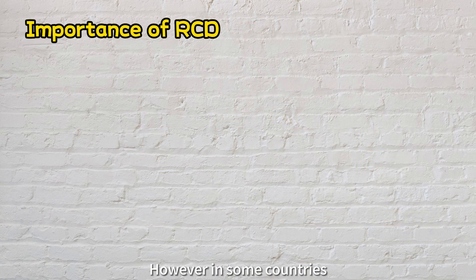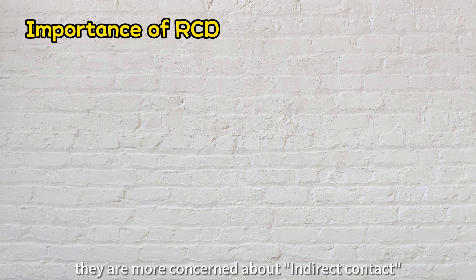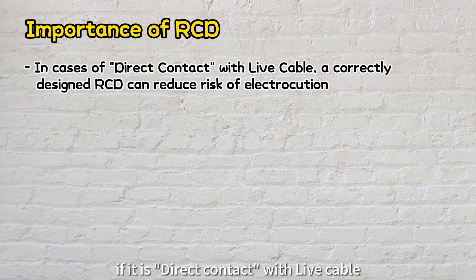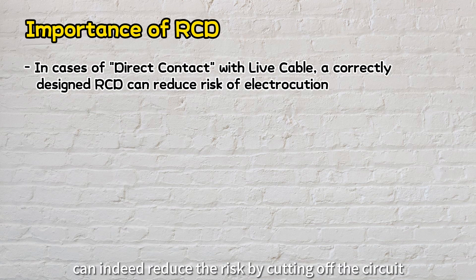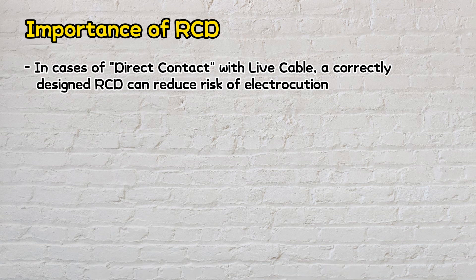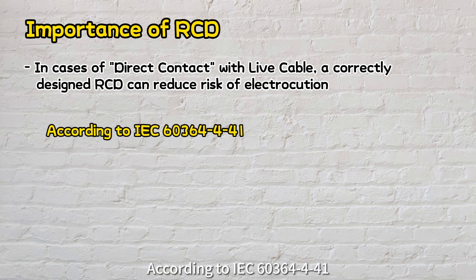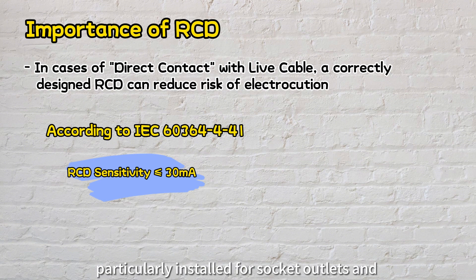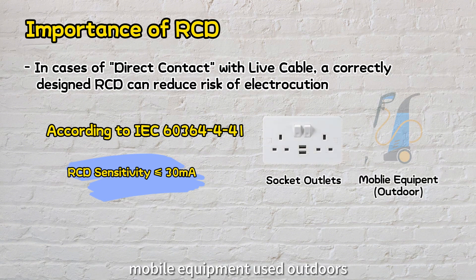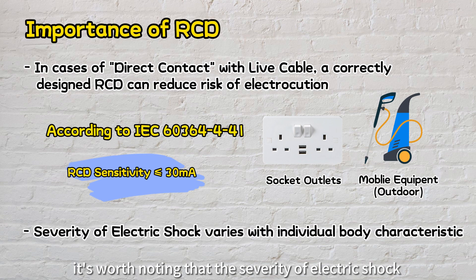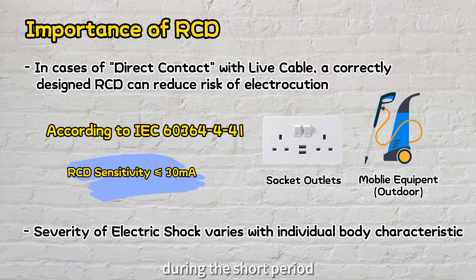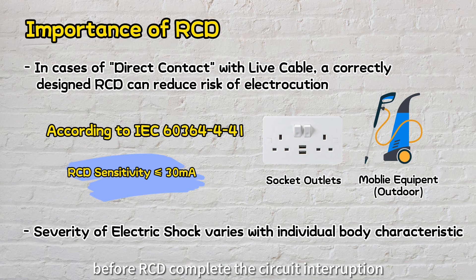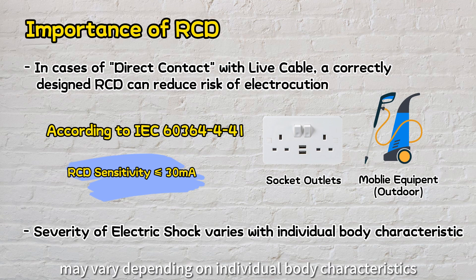However, in some countries, RCD is not considered compulsory as they are more concerned about indirect contact. If it is direct contact with a live cable, a correctly designed RCD can indeed reduce the risk by cutting off the circuit. According to IEC 60364-4-41, the sensitivity of the RCD should be 30 milliamps or lower, particularly for socket outlets and mobile equipment used outdoors. It's worth noting that the severity of electric shock during the short period before the RCD completes circuit interruption may vary depending on individual body characteristics.